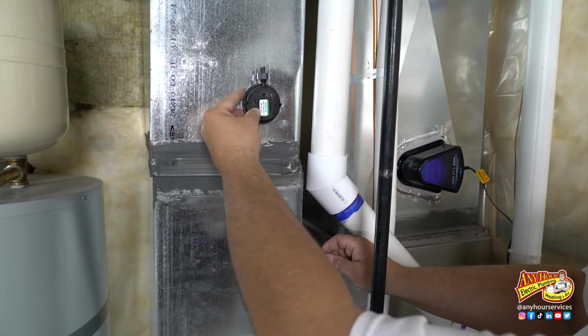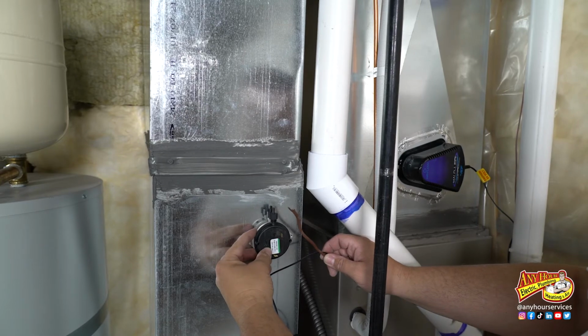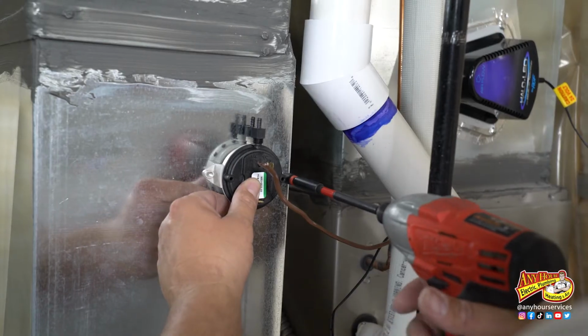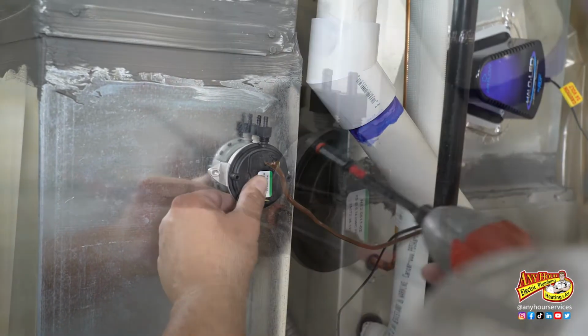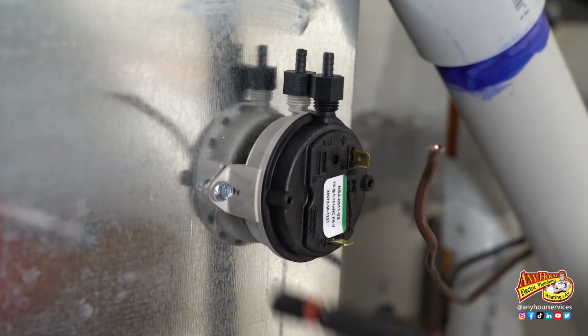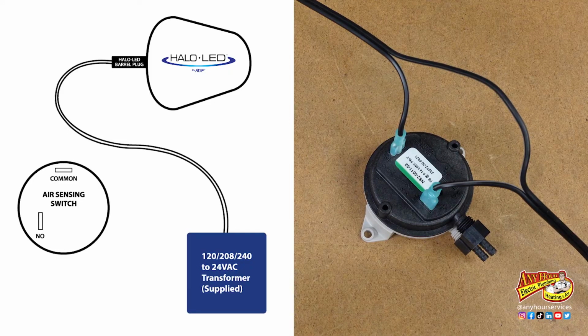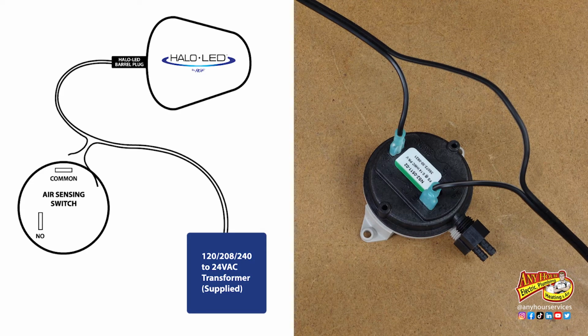If you haven't mounted your air switch yet, go ahead and find a location that you like and mount it now. I usually mount mine to the return duct because there's less vibration and heat there. If the supplied power cord is long enough to reach the air switch and the Halo LED, split one of the low voltage wires and put a 1/4 inch tab on either side. Plug each one onto one of the terminals of the air switch. Doesn't matter which one connects where.